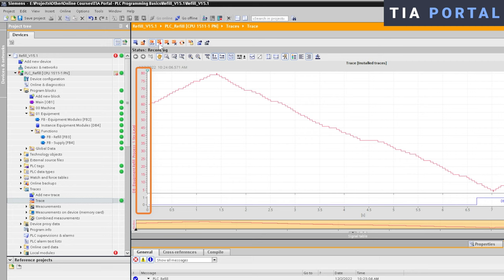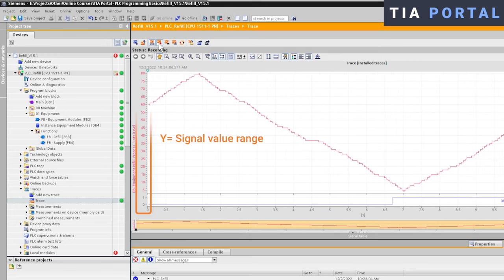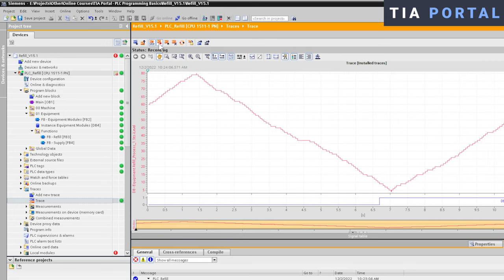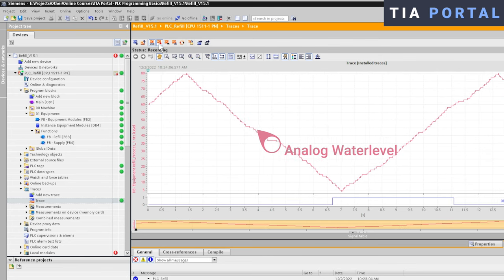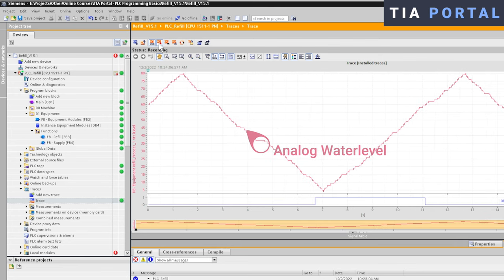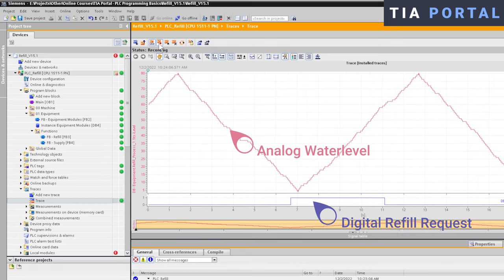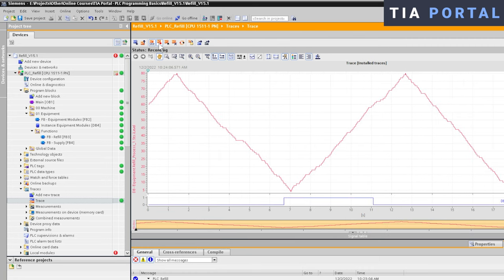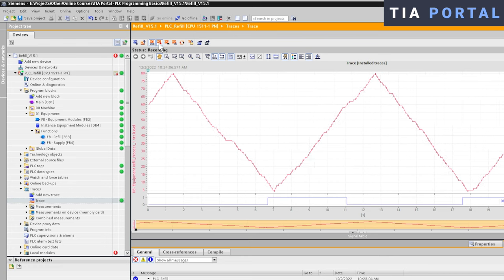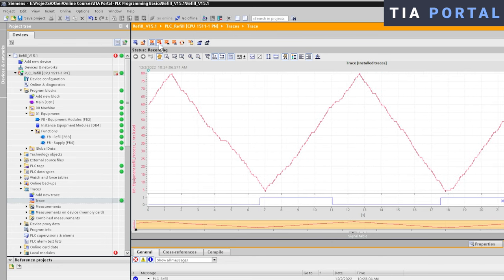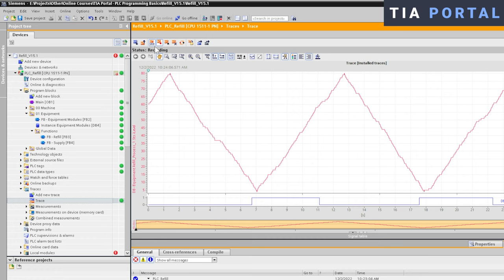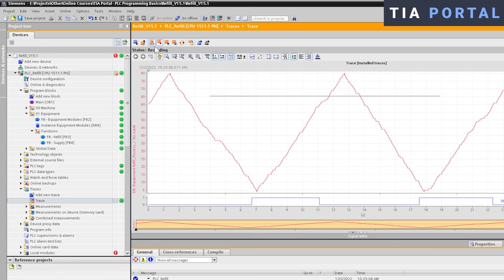You can see here that the analog water level is fluctuating up and down at the moment, and the digital refill request is going high and low. In my professional opinion, traces are an essential part of your toolset as a TIA PLC programmer. I even dedicated a whole lecture to it in my TIA Portal PLC Programming Basics course. So check out the description below this video for more information. When it comes to troubleshooting your Step 7 PLC application, TIA Portal is the clear winner here with the ability to configure and run traces, the single most important tool for troubleshooting your PLC application.